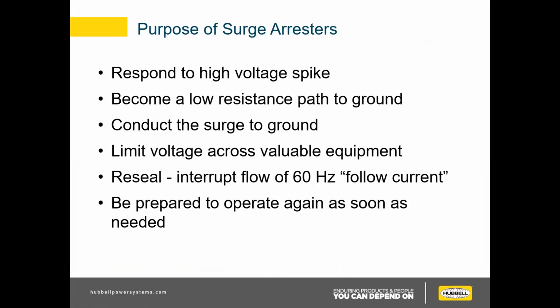So the high level purpose of a surge arrestor is essentially to respond to a high voltage spike. The arrestor sits at line to line voltage or line to ground voltage at really high resistance. When a lightning strike happens or a switching surge or any kind of impulse comes, it turns into a low resistance path to ground. And so it conducts the surge to ground and limits the voltage across the equipment, whether that's a transformer or a cutout or anything really. And then it has to reseal the follow current of 60 hertz current so it can operate again, for the next lightning strike or any switching surge, any kind of impulse, it is ready to operate again.